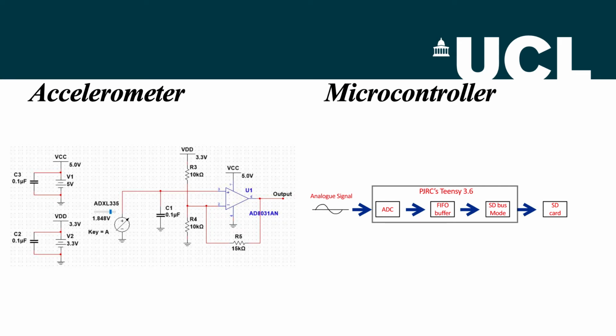For the accelerometer, amplification is required to satisfy the maximum resolution of the ADC, but also between 0 and 3.3 volt at the same time. The analog signal from the audio and the accelerometer first flow into a 12 bits analog to digital converter. We are using the same sampling frequency at 50 kHz for both the audio and the accelerometer. Then the digital signal goes into a first in, first out buffer and stored in the SD card through the SD bus mode.